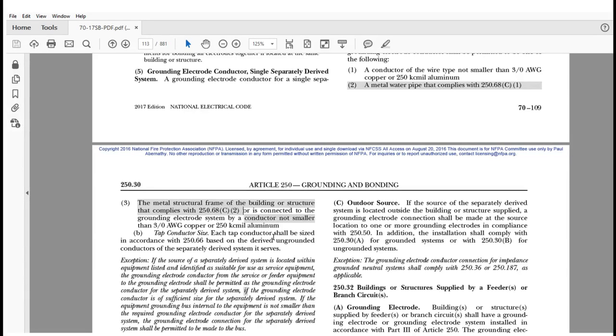All right. Again, the revision code reference in 250.68(C)(2) that was added relates to the metal structural frame of a building or structure being used as a conductor to actually interconnect the different electrodes as part of the grounding electrode system, not so much as the electrode itself. Okay.